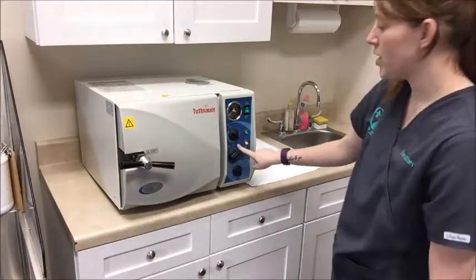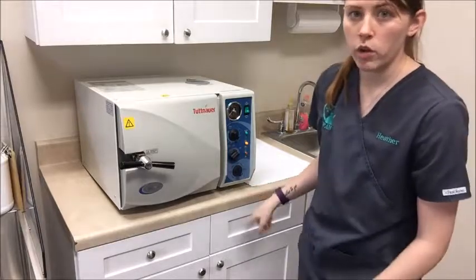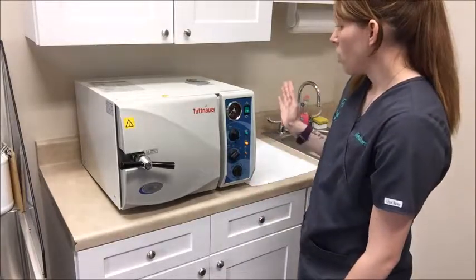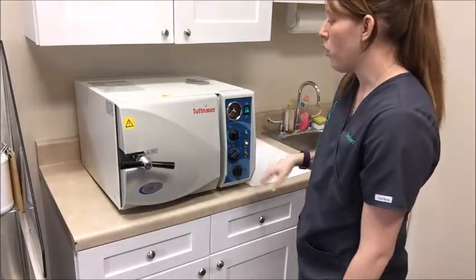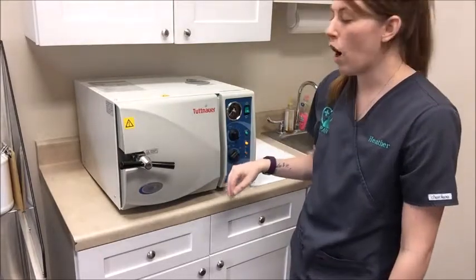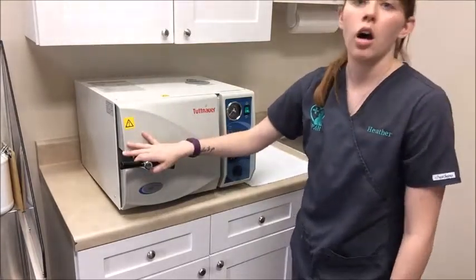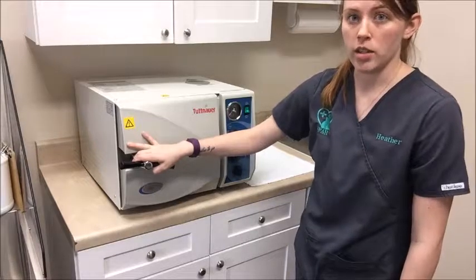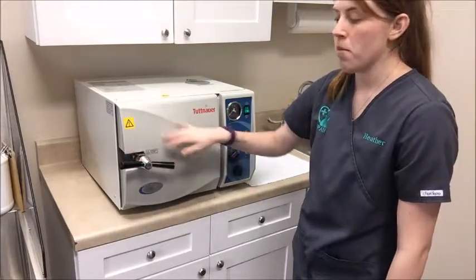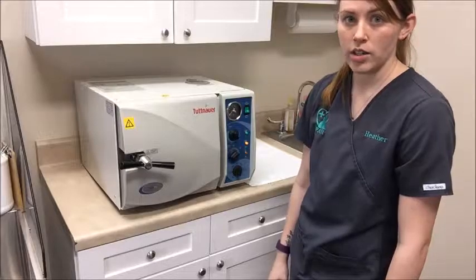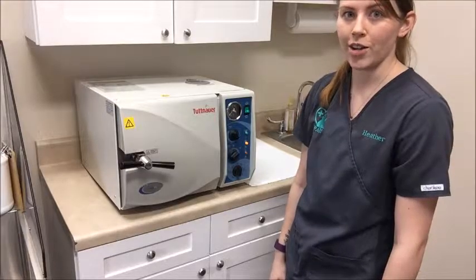And then once that 30 minutes is up, I'm going to manually exhaust the unit, which will let the pressure relieve. And then once the pressure is all the way down to 0, I'm going to just crack the door and then set a drying cycle for 30 minutes. So I'm going to come back in 30 minutes and we'll go ahead and get the unit exhausted and start the drying cycle.